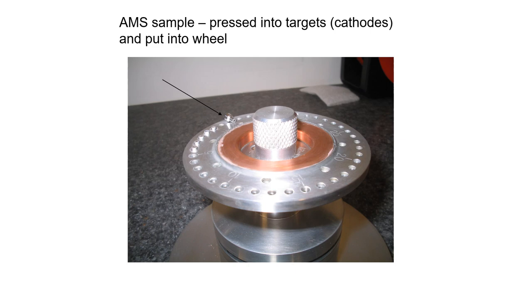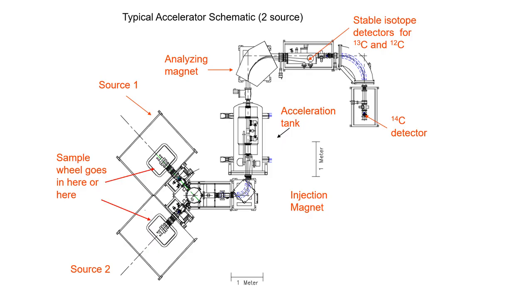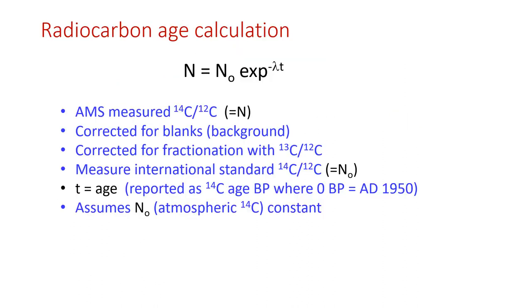The sample is then pressed into what we call a target or cathode and put into a wheel to go into the AMS. This is a typical schematic of an accelerator with two sources. The sample wheel goes in either here or here. It's then ionized and goes through a series of magnets, an accelerator tank, and finally an analyzing magnet that separates the stable isotopes carbon-13 and carbon-12, while the carbon-14 goes on to a detector where the carbon-14 atoms are counted.